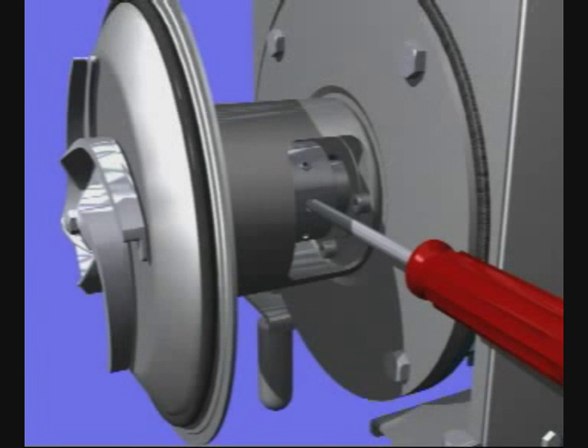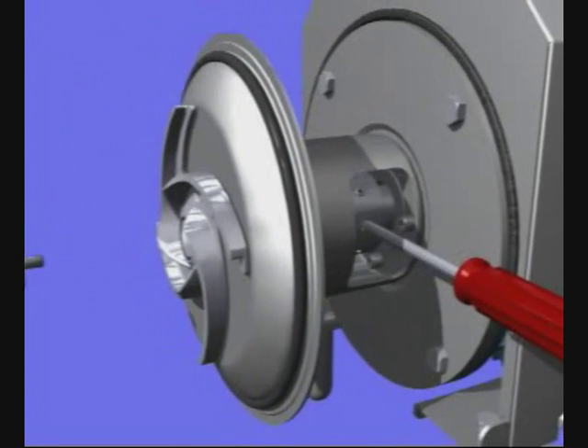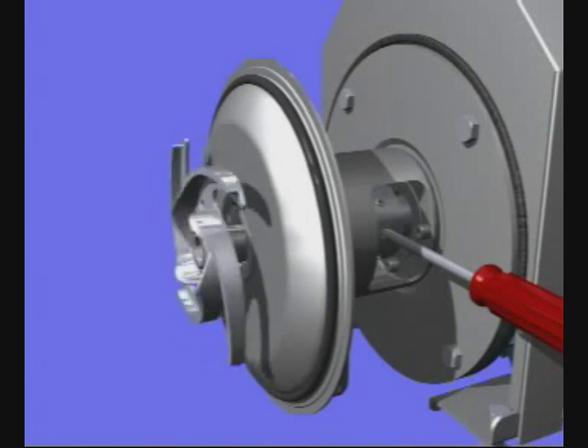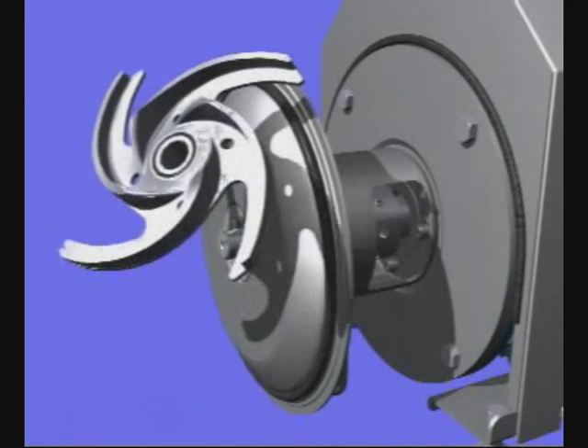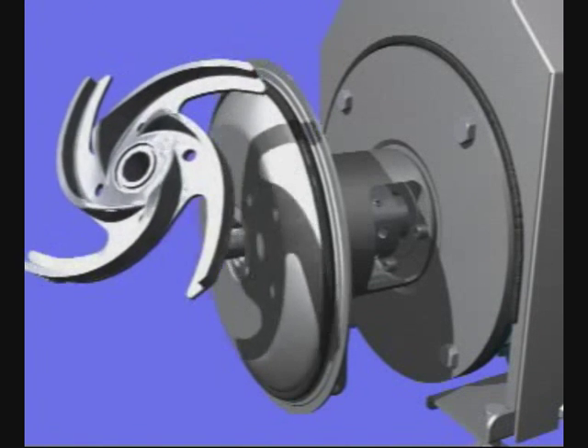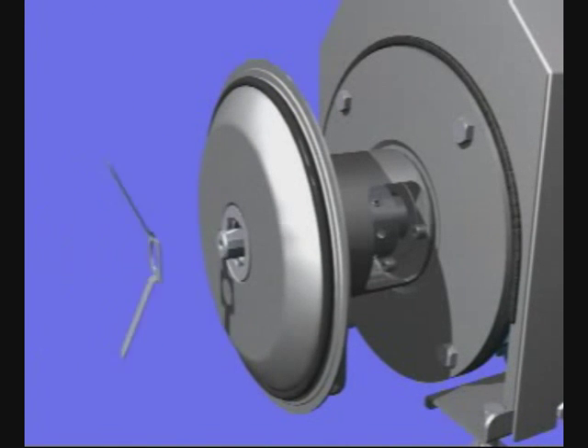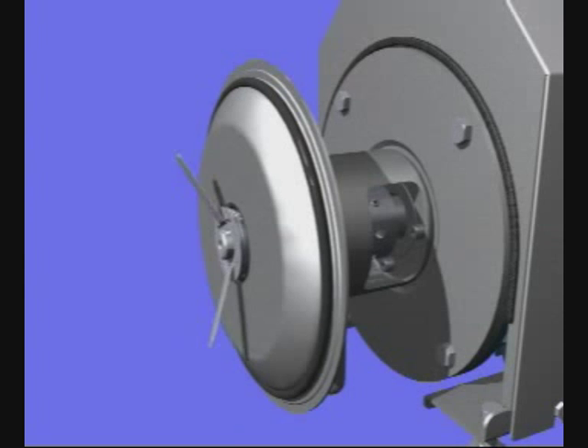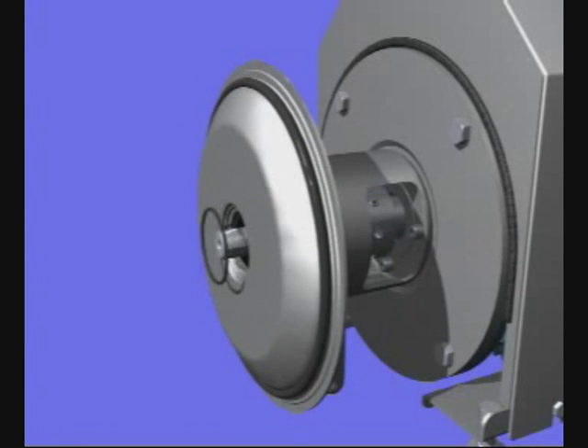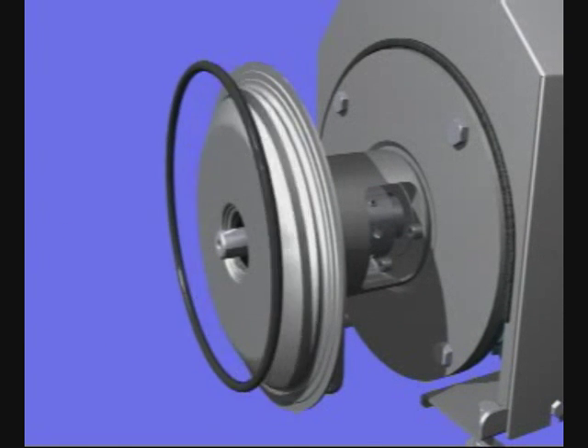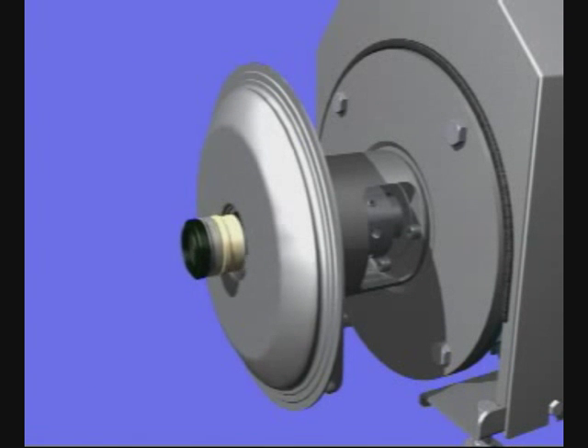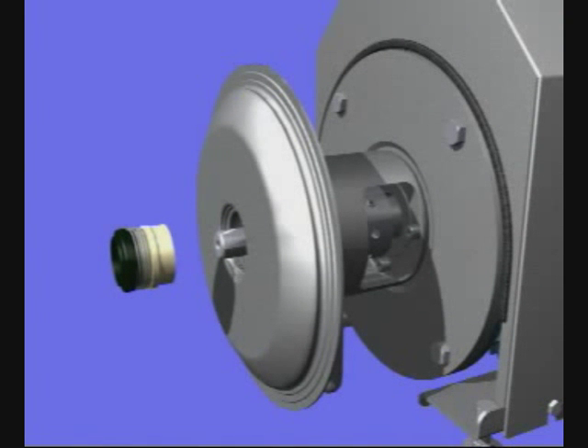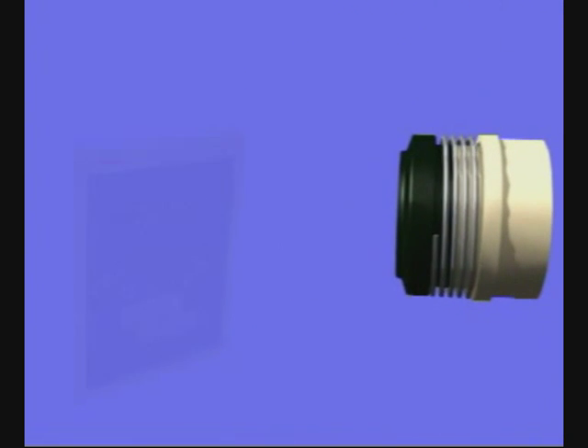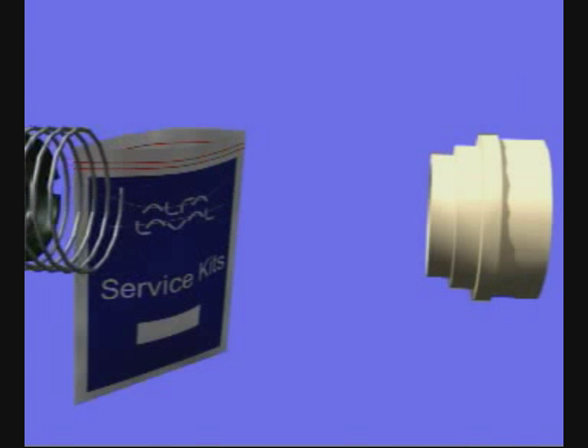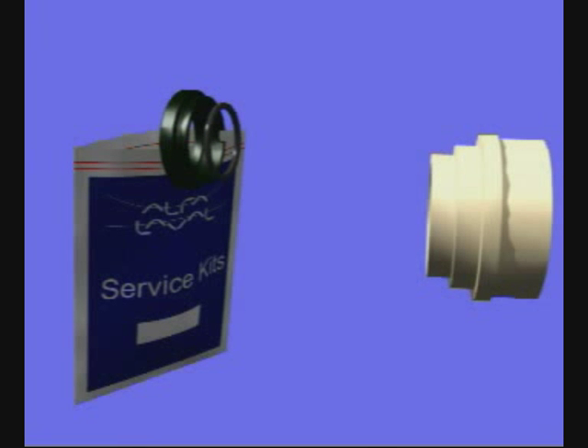Fix the shaft with a screwdriver and remove the impeller screw and impeller. Remove the O-ring. Unscrew the stationary seal with the tool supplied with the pump. Remove the O-rings. Take out the remaining shaft seal through the hole in the back plate. This front-loaded design allows you to save valuable time. In the service kit, you will find all the necessary wear parts required for servicing.